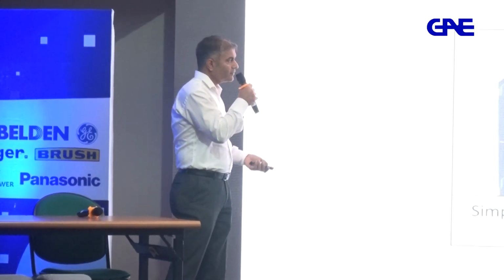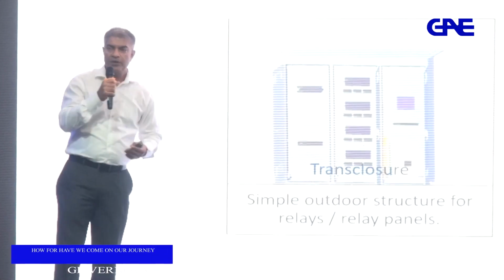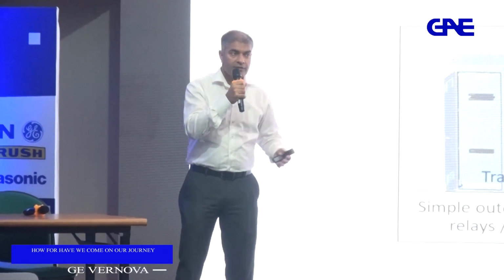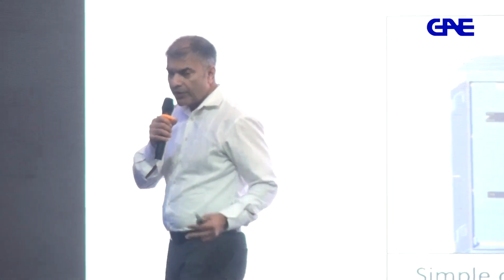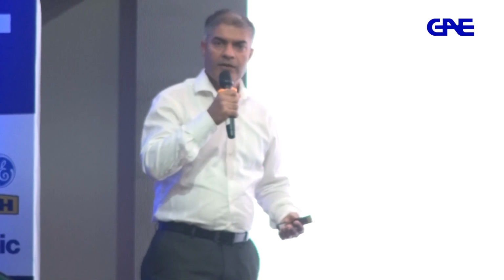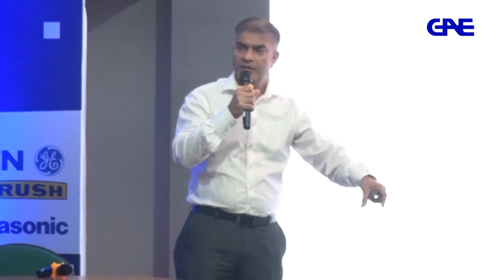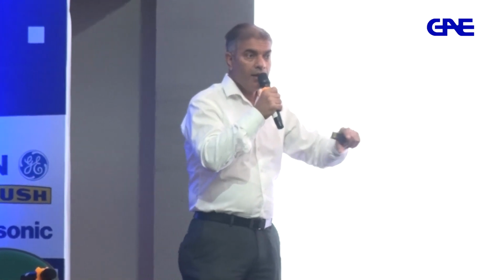Pre-tested structures. So this is what some customers do, that they have a plug-in control house. So for example, in a brownfield substation, when you want to refurbish the secondary system in a substation, what they do is that they build this control house, the control building, and they commission that control building as a whole while the substation is running. So during refurbishment, they just drop in the control building in a substation, connect all their fiber optic network, and the building is ready. And as and when you want to cut over all the feeders, okay, from the conventional system to digital, it can be done very, very quickly, okay?